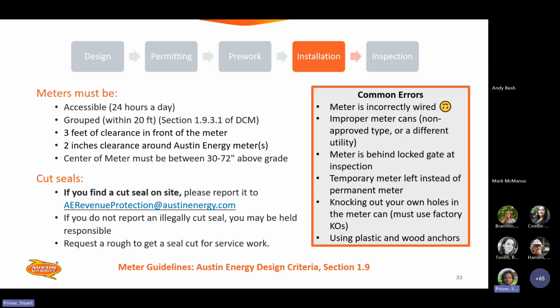We've had some instances in the past where revenue meters have been installed and then a customer finishes some landscaping and all of a sudden that number changes. So it's a good thing to check at site assessment to make sure that the revenue meter is actually within that range. If you see a cut seal, you should stop work and tell us about it at that email address there, AE Revenue Protection at austinenergy.com. And if you don't report the cut seal, you may be held responsible for it. So keep an eye out for that.